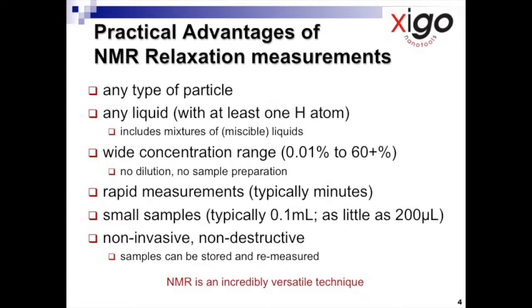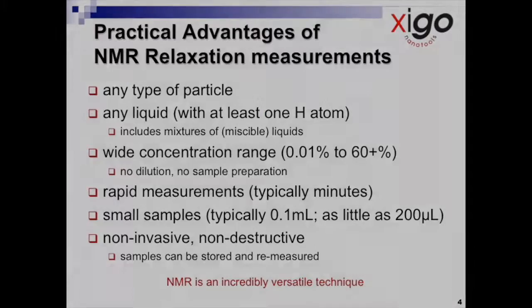Of course, it depends upon the sample under investigation and the precision required, but measurement time is typically less than five minutes. Only a small amount of sample is necessary, around 0.1 millilitre. And importantly, the technique is non-invasive and non-destructive. This means that samples can be stored in the NMR tube and then reanalyzed at any later date. NMR is indeed a very versatile technique.